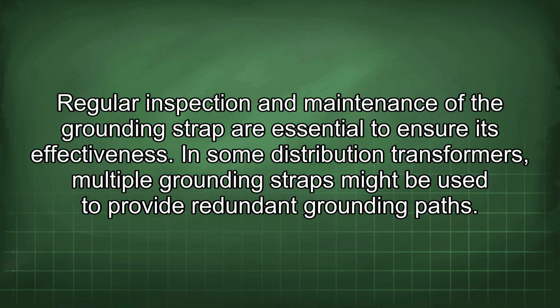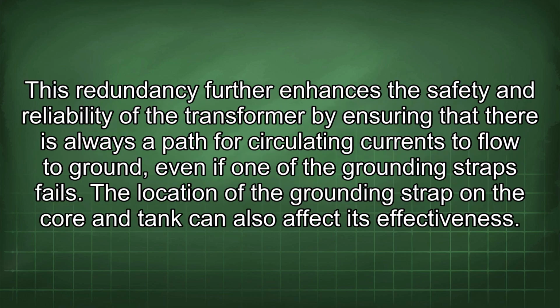In some distribution transformers, multiple grounding straps might be used to provide redundant grounding paths. This redundancy further enhances the safety and reliability of the transformer by ensuring that there is always a path for circulating currents to flow to ground, even if one of the grounding straps fails.